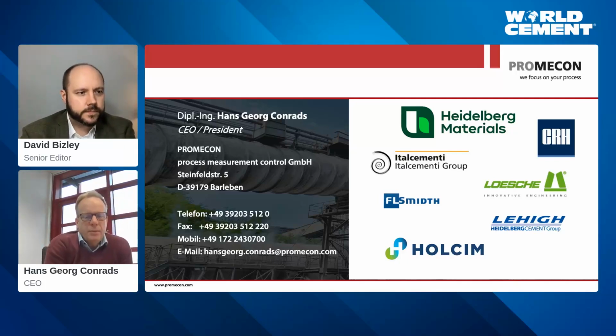Yeah, very good question. Happy to answer that. PROMECON is not only measuring process gas for the cement industry, we are also in the steel industry and other smelter industries. And in these industries, we are measuring with the infrared sensors CO2 content, CO content, and certainly SO2 content is possible. The thing, however, when you talk about pollutants, is the levels. We are a process gas measurement company. So when we're talking CO measurement, we're measuring 2%, 5%, or 15% CO in a steel plant. We're not measuring ppm. That's way too small. So if you want to know SO2 on a large level, on a percentage level, that would be possible. If you are talking SO2 on the stack at ppm level, that's not. We're not doing CEMS. We're really focused on process gas only.